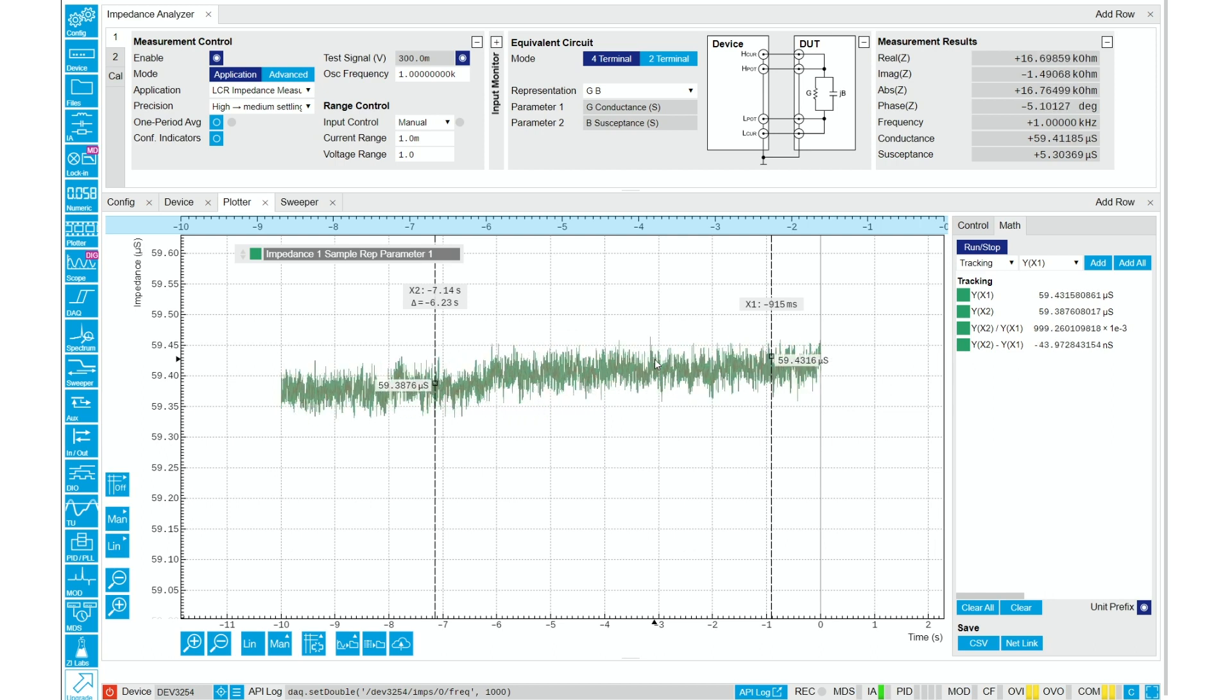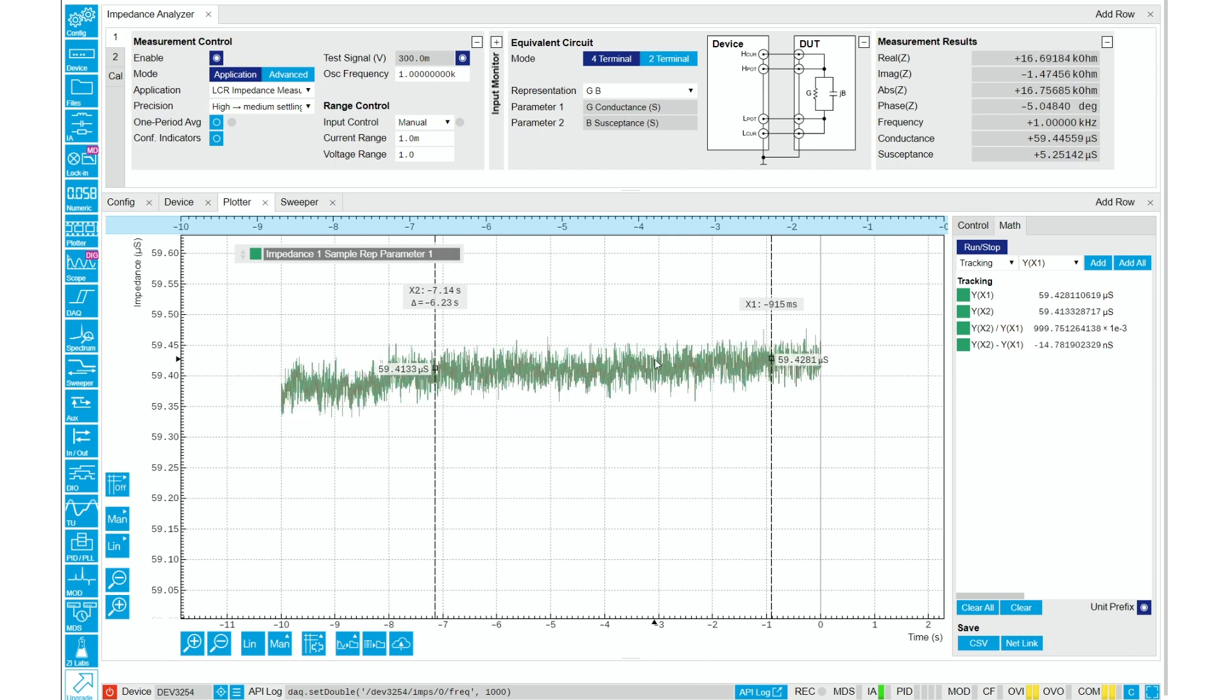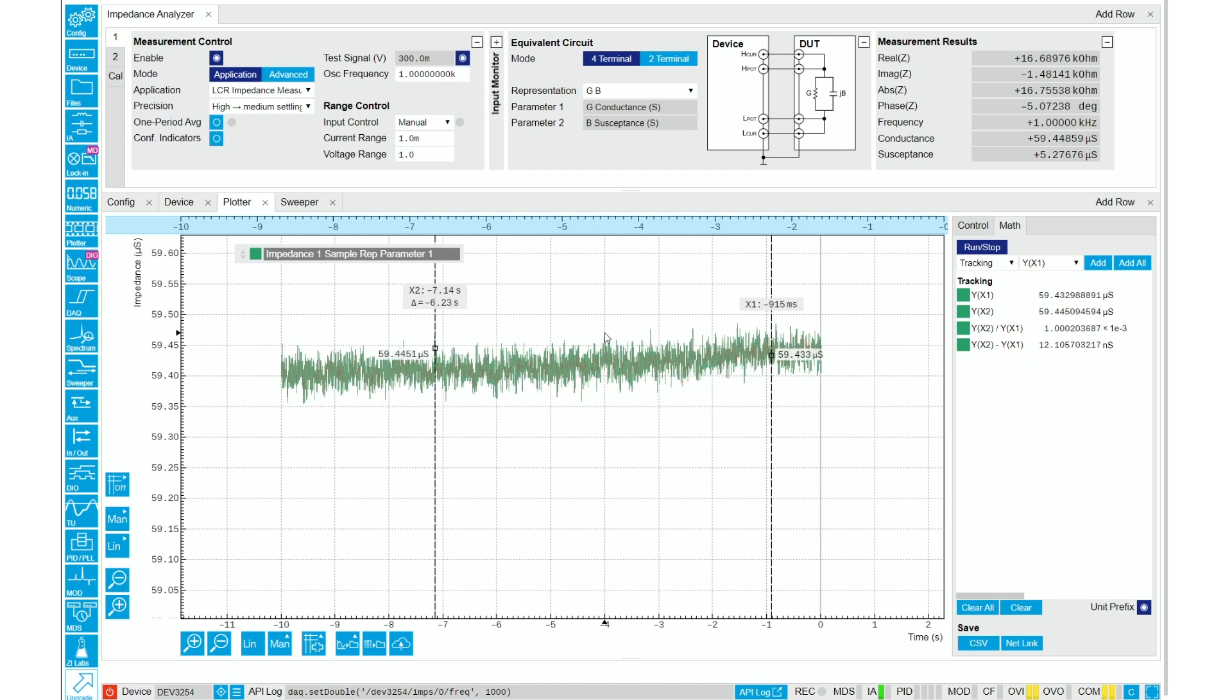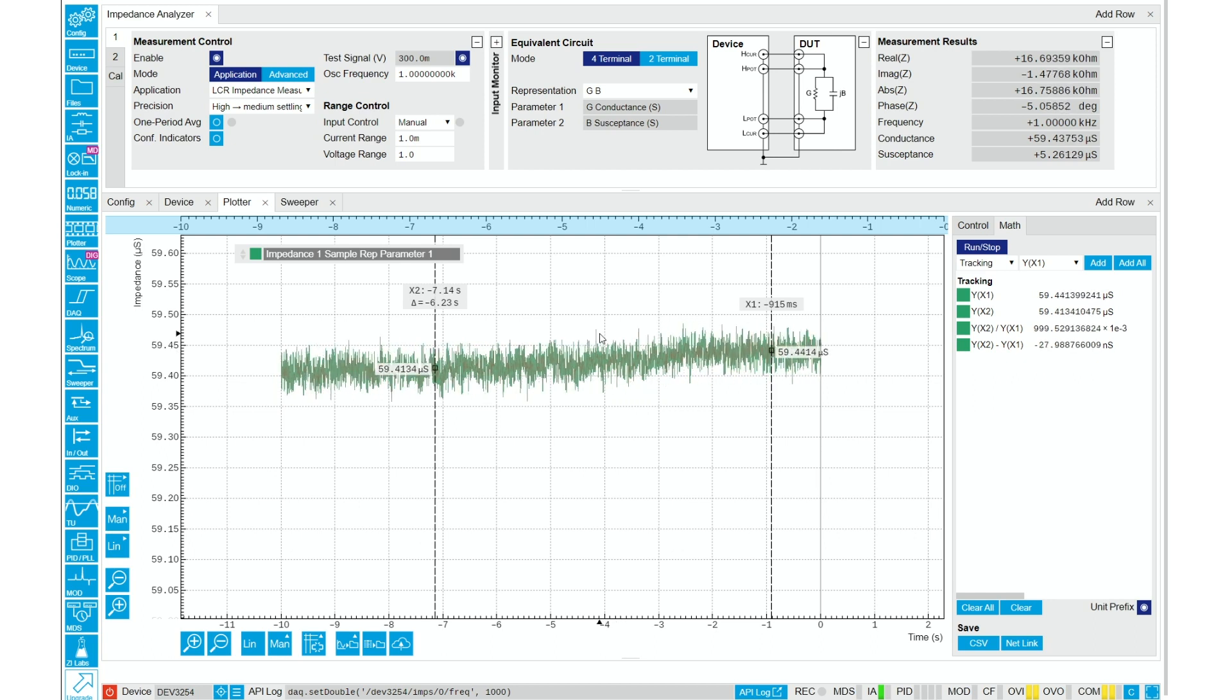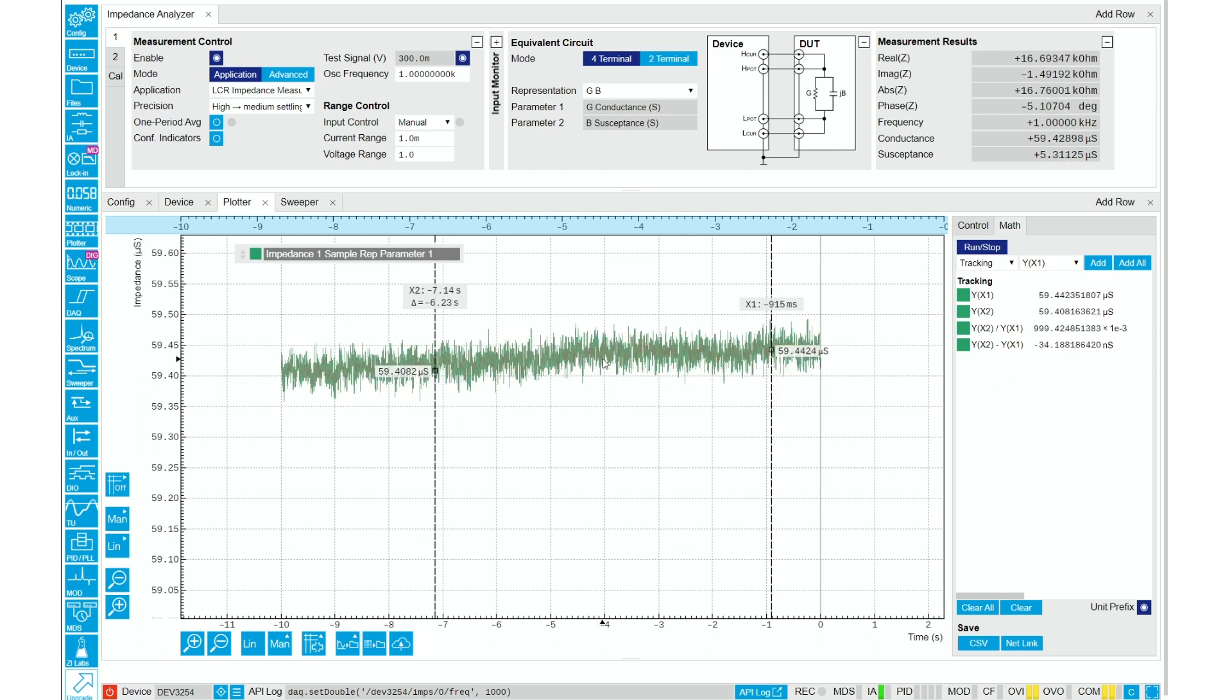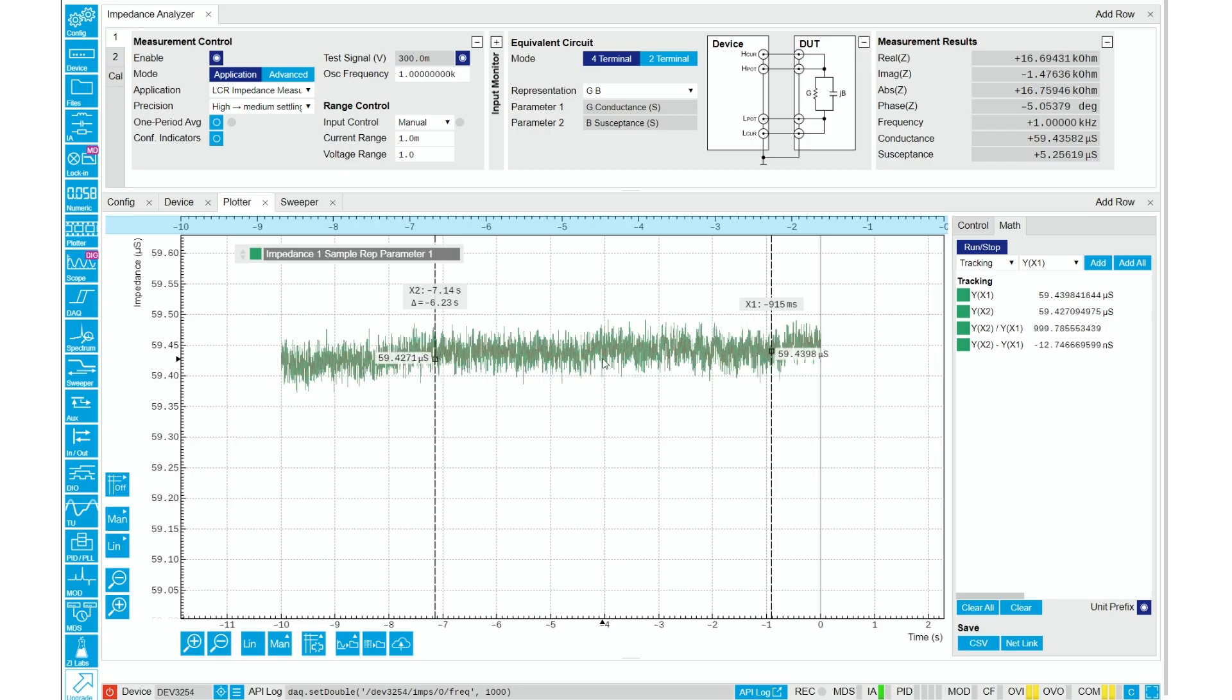However, note that there are also other circuit elements, such as double-layer capacitance in this circuit. As such, this probe cannot be used for accurate loss measurement.